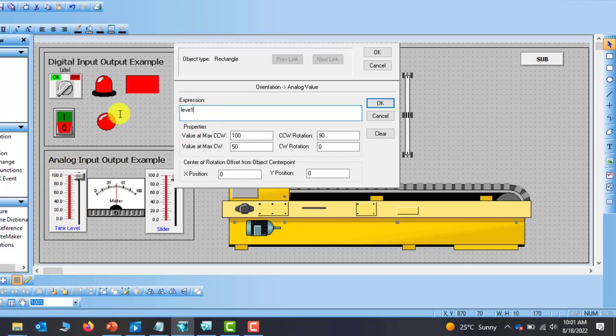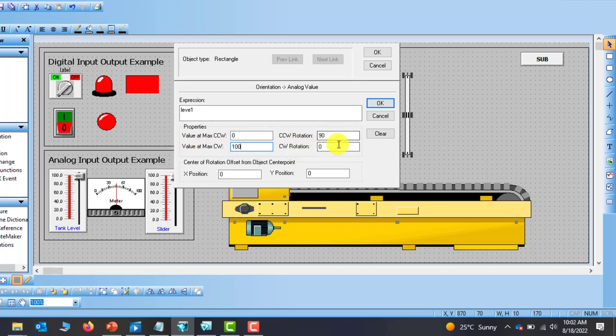The expression will take that particular tag, so I place the tag there. Under the properties you have to give the range of the data that you use for the control. For now we have 0 to 100, so I'll specify 0 here and then 100. For the rotation, you can choose 360, 180, 90, or 45 degrees. For now we want to go 360.